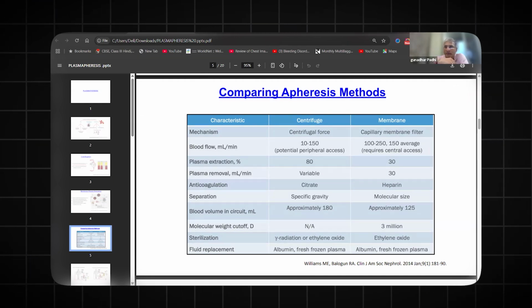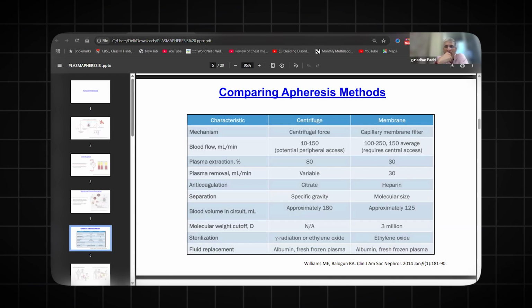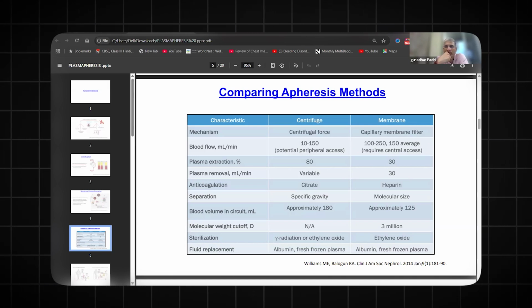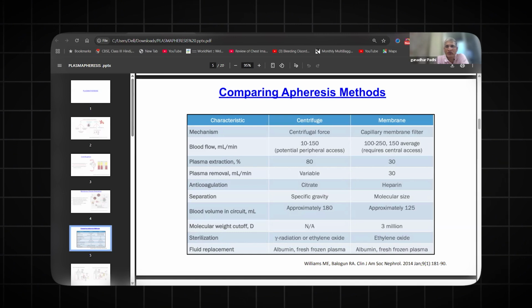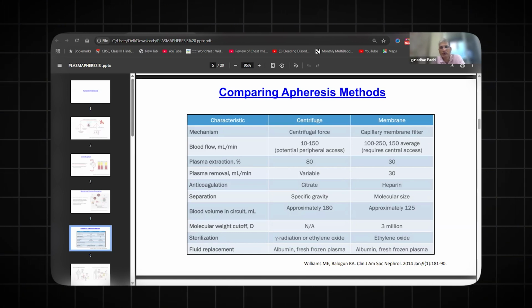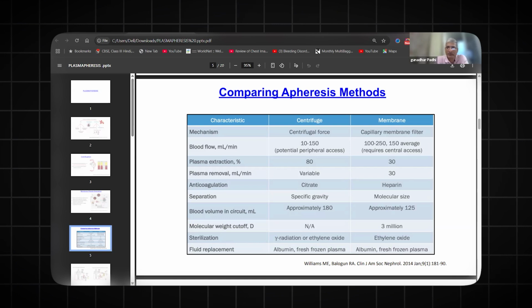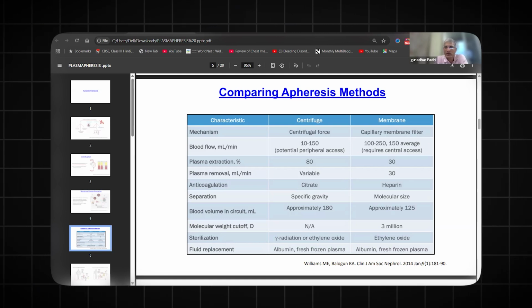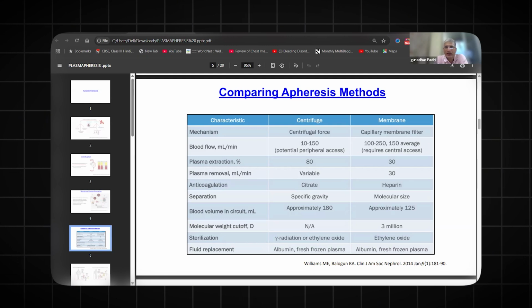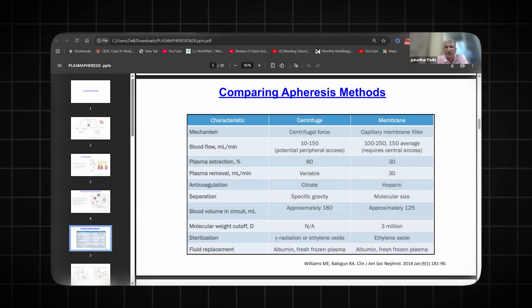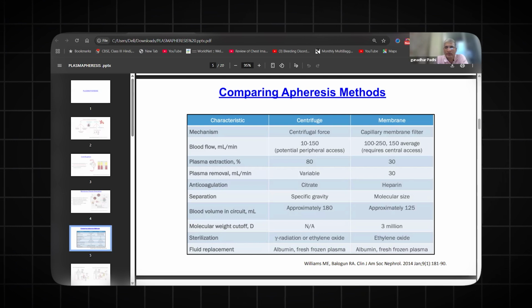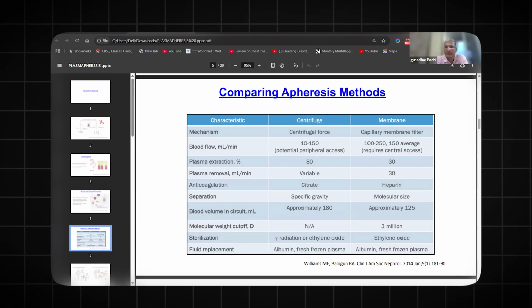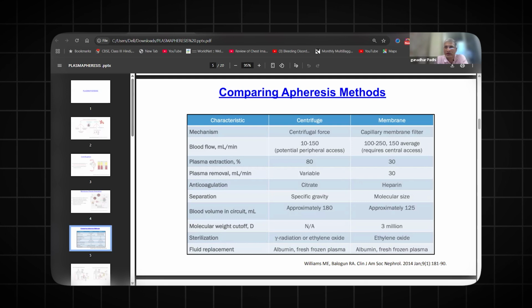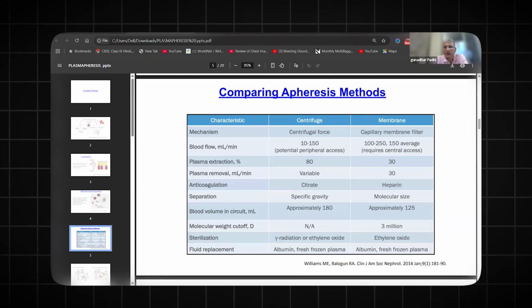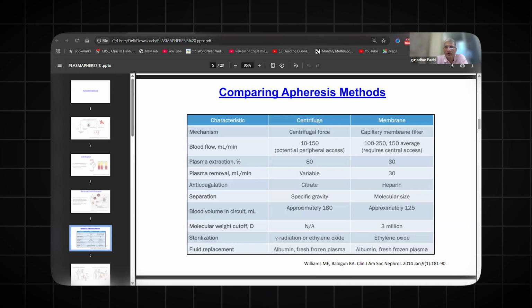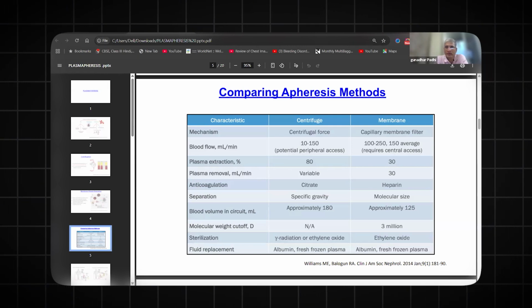It depends on your filter type. So these are the comparisons of the different modes of the apheresis technique. One is the centrifugal technique versus the membrane technique. The centrifugal technique works on centrifugal force. The membrane technique works on capillary membrane filtration pressure. And here the blood flow rate is very important, because in membrane filtration you will require a slightly higher blood flow rate to filter things out, compared to the centrifugal pump, where the blood flow rate can sometimes be kept low.